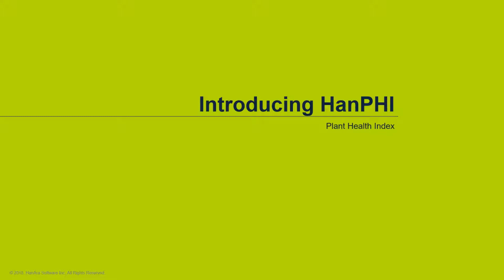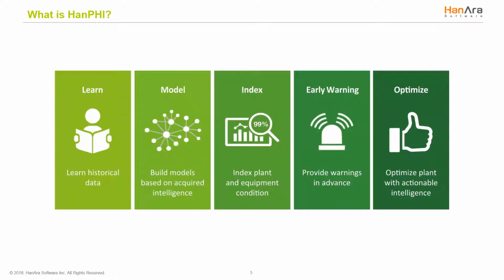If you're ready to add advanced pattern recognition into your strategy, our Plant Health Index solution, HanPHI, alerts users of potential problems at a plant before they occur. It focuses on the current condition of the plant, not the ideal plant that exists in a vacuum. HanPHI uses an empirical data model that learns historical, fault-free, normal operation data to create patterns. This solution identifies small deviations in equipment and operation behavior that are precursors to potential and/or hidden failures.